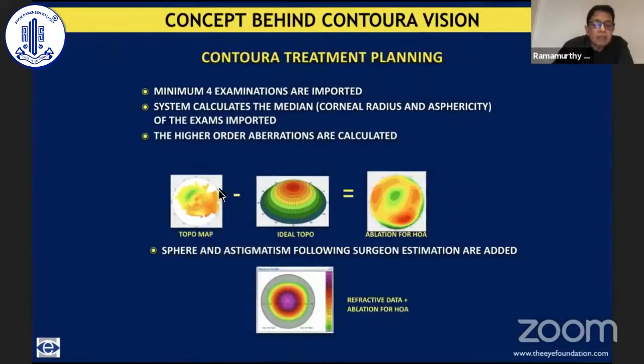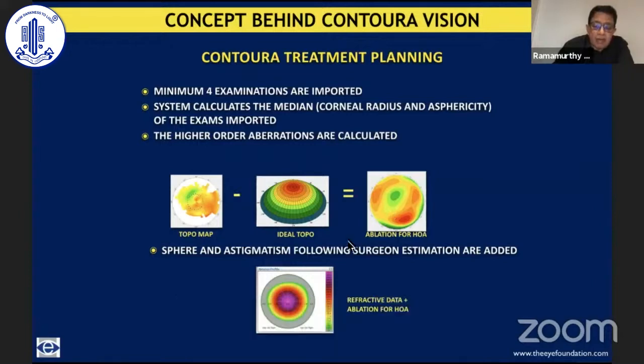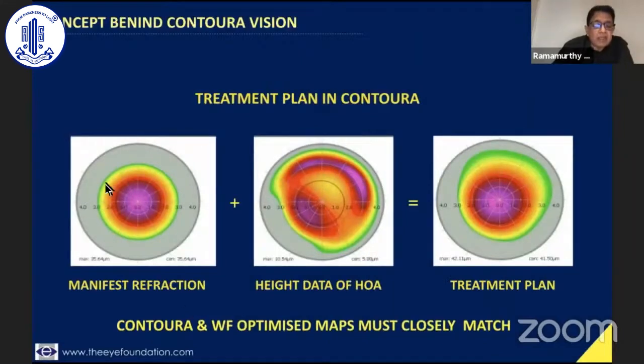This is the basic concept. A topo map is acquired by the Topolyzer; this is the ideal topography you want to achieve. This ideal map is subtracted from the acquired map, and this becomes the ablation profile for the higher-order aberrations, which is combined with the basic treatment profile needed for correction of the refractive error. The final profile applied to the cornea for correction of both the refractive error and the higher-order aberrations of the so-called normal non-aberrated cornea becomes the Contoura treatment. One key check: we make sure that the wavefront optimized profile and the final Contoura profile are somewhat similar. If there is a wide variation, that is a relative contraindication for use of this profile.